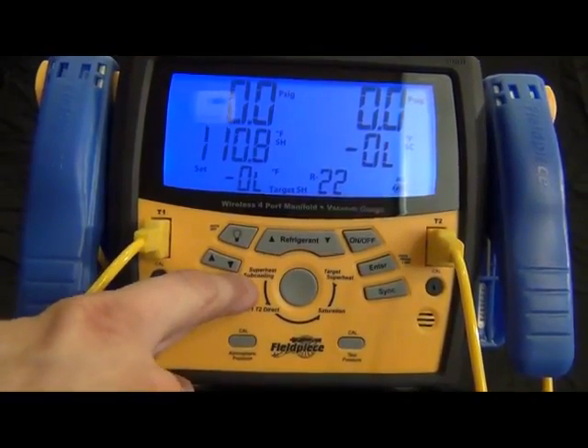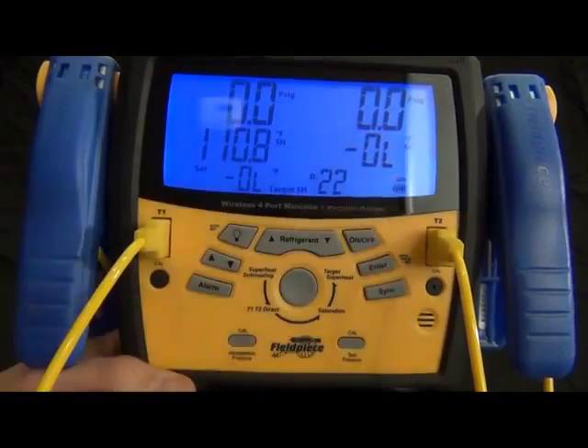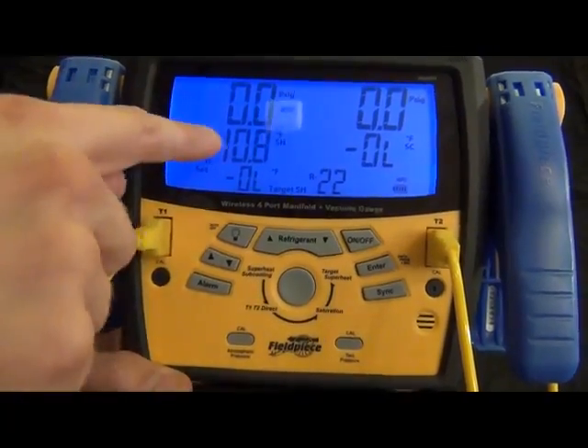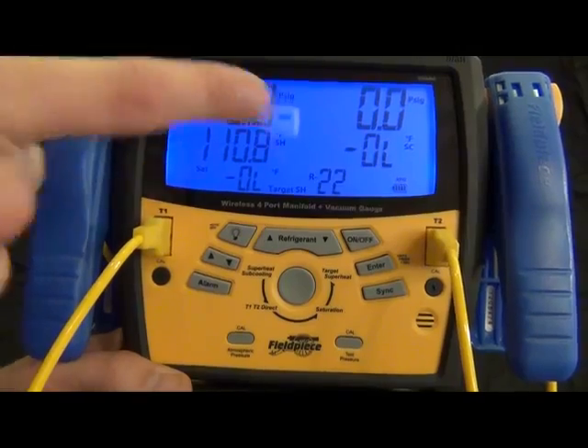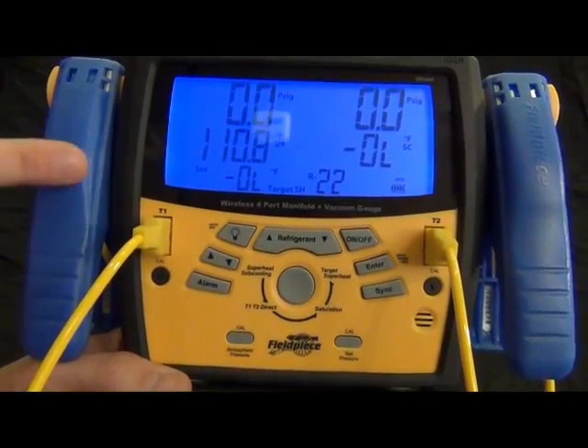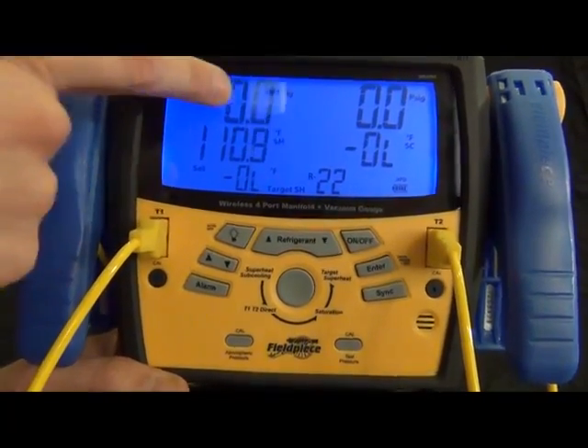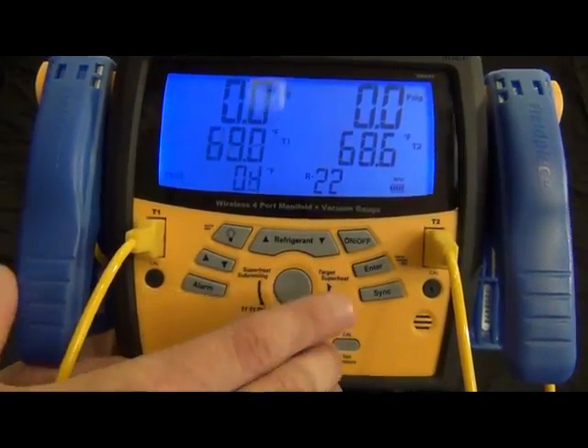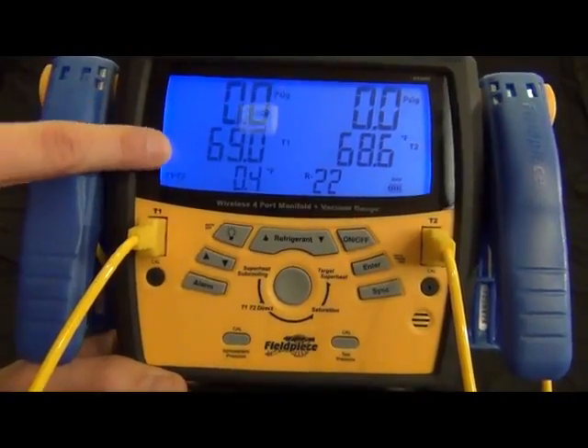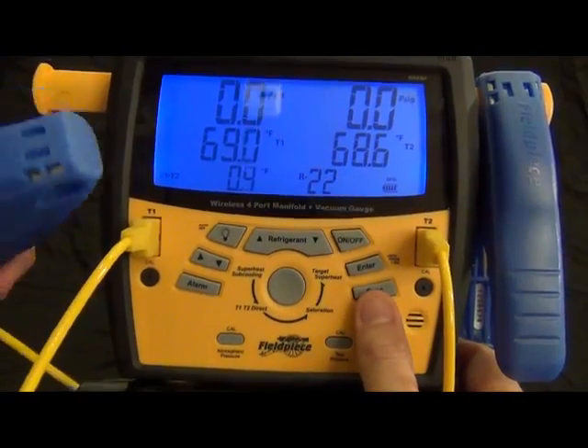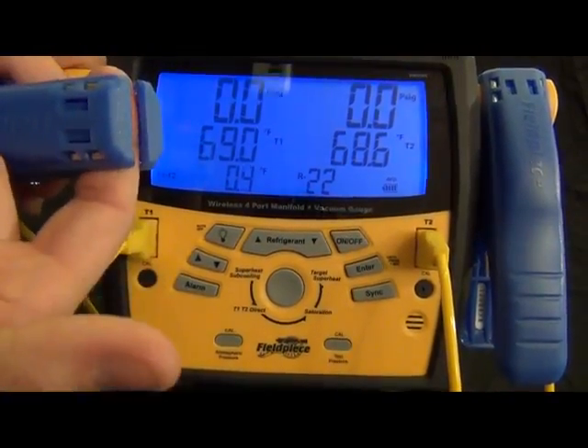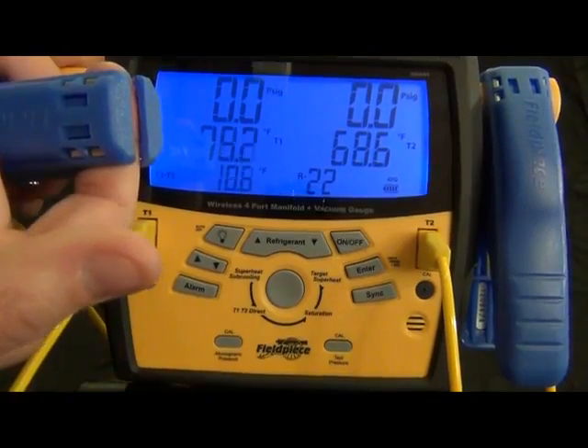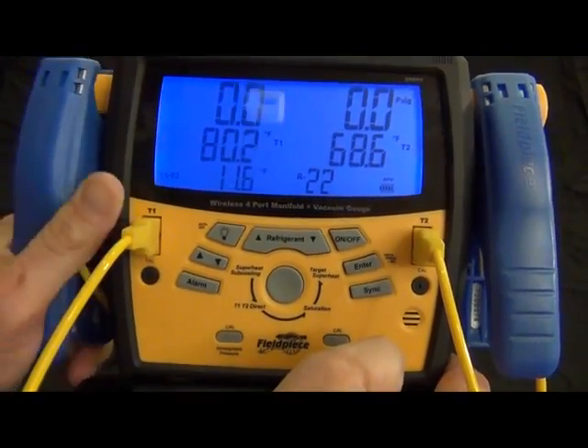So right now we're in superheat and subcooling. How you can tell that is by the SH and the SC right next to the mode. So what this 110 degrees of superheat is saying is my pipe temperature of around 70 degrees and at zero psi produces a 110 degree superheat. To see that, a 69 degree temperature. That's the actual measurement of this clamp is taking right here. So what I can do is kind of just show you how it creeps up. I'll just warm it up a little bit with my finger and you can see it climb really fast.